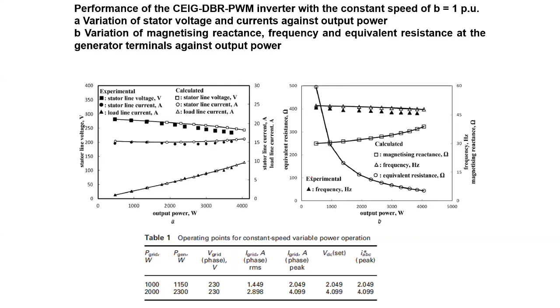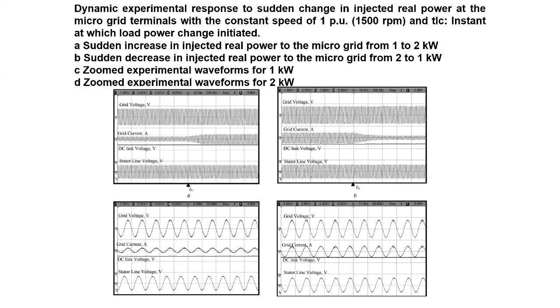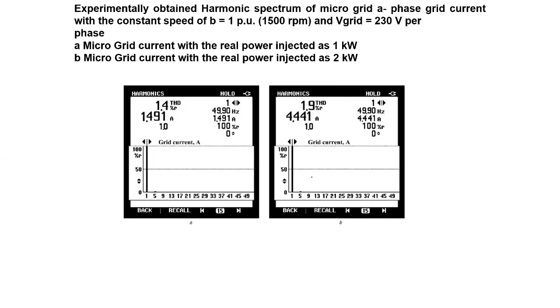This is the experimental validation, like a sudden increase in real power to the microgrid. We considered from 1 kilowatt to 2 kilowatt and 2 kilowatt to 1 kilowatt, to check whether we are able to maintain the sinusoidal shape of the current at the grid terminal. Since we used a diode bridge rectifier, the DC link voltage will continuously vary. Power quality was tested at the grid terminal, but the drawback is power quality is not maintained at the generator terminal. Using a back-to-back power converter would definitely improve the power quality.